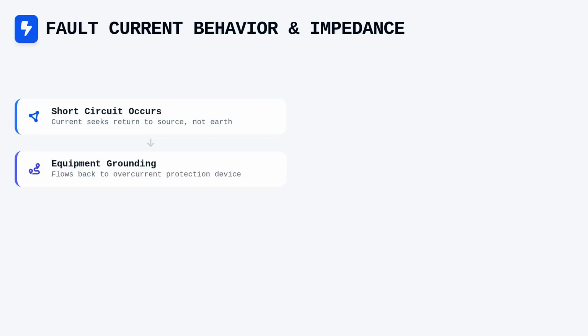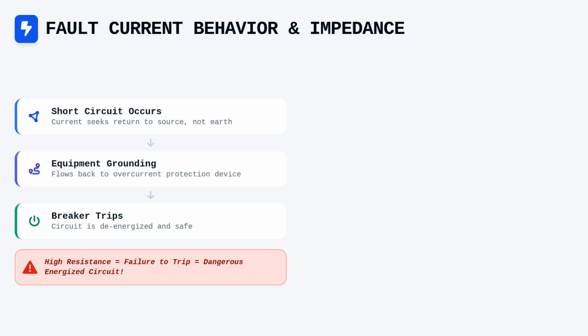Understanding the behavior of fault currents is essential for any designer, as current always seeks to return to its source, not the earth. When a short circuit occurs, the fault current flows through the equipment grounding conductor back to the overcurrent protection device, which triggers the breaker to trip and de-energize the circuit. This fault-clearing process relies entirely on the impedance of the path. If the path has too much resistance, the current may not reach a level high enough to trip the breaker, leaving the circuit energized and dangerous.